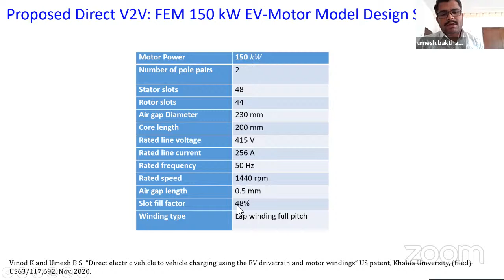So we designed a 150 kilowatt simulation model using Ansys Maxwell FEM. It's a 4-pole machine with 48 slots and rotor slots, and all the dimensions of the machine design can be done there. It's a lap winding with full pitch.